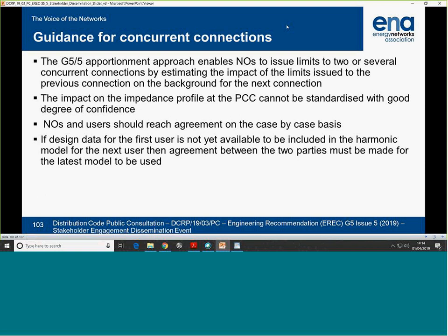If you had to make an offer to somebody coming along, would you say to them, this is what you can do, but there's a window of uncertainty here because customer A hasn't connected yet and we haven't had a chance to verify? Well, the sources of error are those which are listed. The method may not be right. When we determine the operational condition of the network, i.e. outages, all these impact the limits we calculate. When we modify the background at different nodes by the limit I issued to the first one, the actual behaviour may not follow the rule I'm using. But that's the only tool I have from the international guidance.